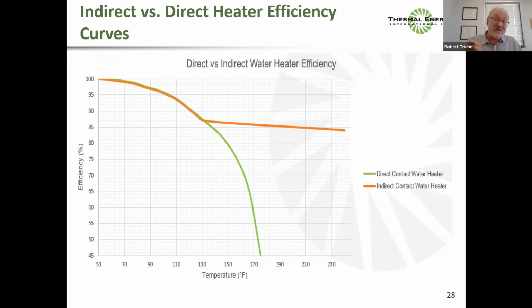No, it's just that your waste heat is now latent heat instead of sensible. So be very cautious with direct fired water heaters, because if you are exhausting above the dew point, one, you're evaporating water, and you should never run in evaporative mode. Your control system should make sure you avoid that. And two, your efficiency is dropping exponentially. And should you happen to go out at 170 F, you're just between 55 and 60% efficient.